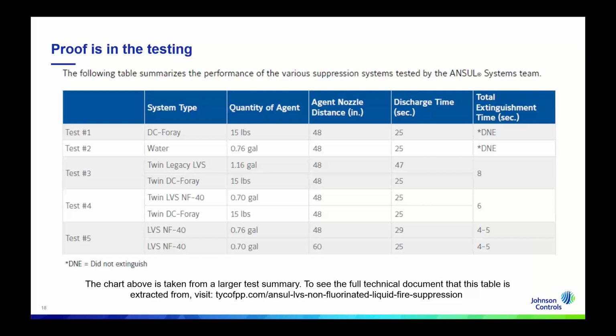You can see in that white paper the different charts that support the cooling and extinguishment times shown here. All of these tests were completed in efforts to push beyond the industry standard test procedures from those third-party approvals we talked about, to understand the impacts of the liquid agent on superheated surfaces when something like a hydraulic line ruptures, or you have a high pressure spray of fire onto superheated surfaces.